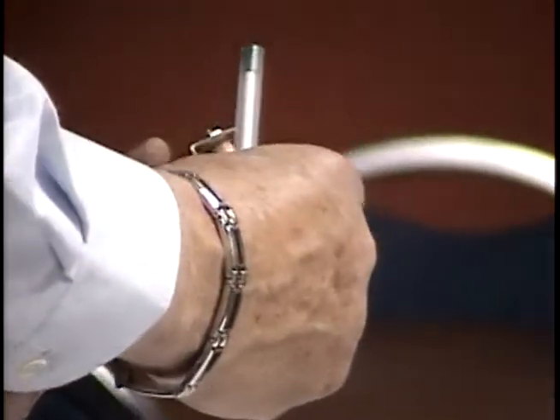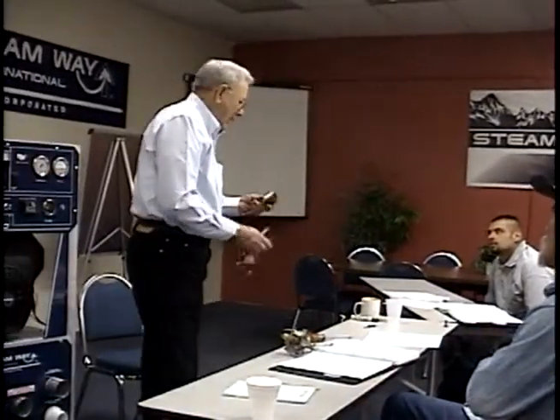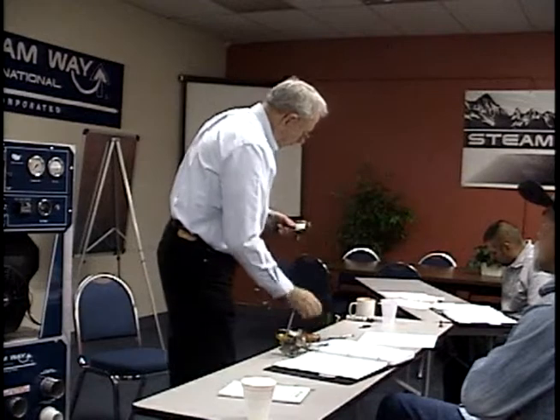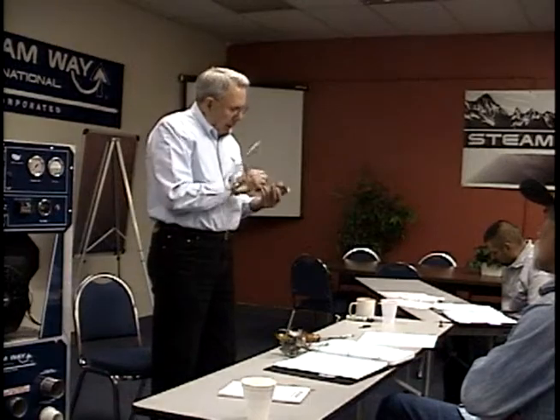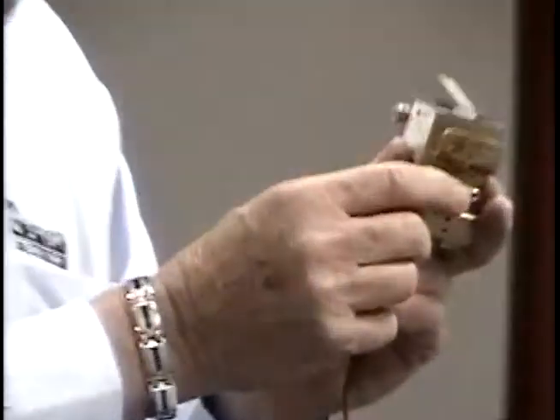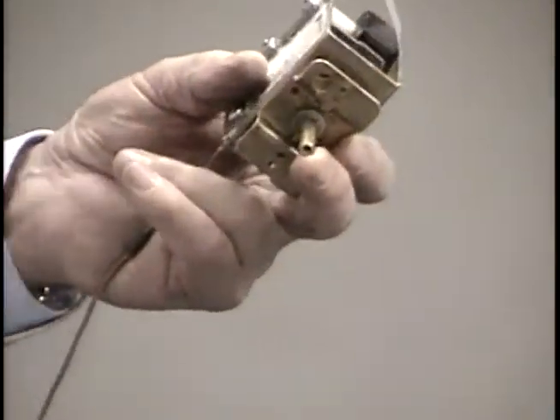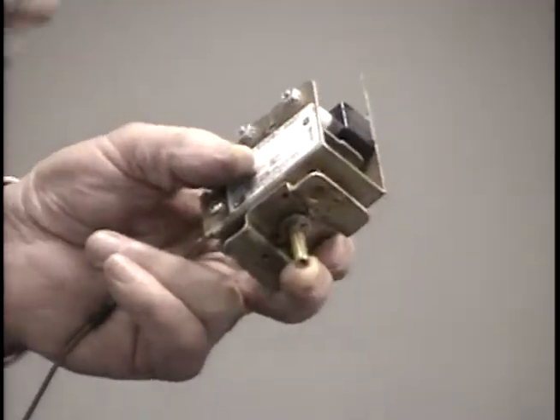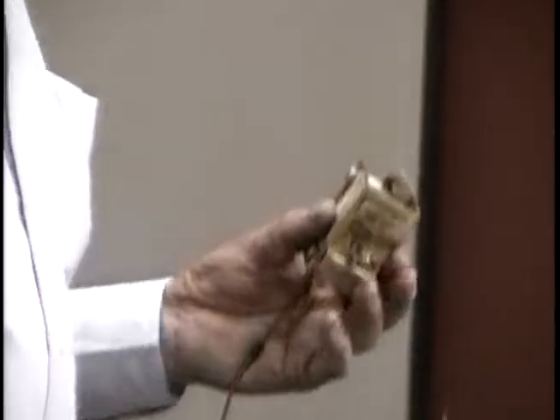See the little round bronze plate? As it swells up, it kicks the switch off. As it cools down, it kicks the switch back on. So this circuit is really more mechanical than electrical. The only electrical part is the switch closed, switch open, just like we saw on our diagram. By the way, we recalibrated those, and they can be recalibrated by taking the knob off, and up through the little hollow shaft you put an Allen wrench in there, and they can be recalibrated. If you got a heater overrun or something that threw it out of calibration, you come back and recalibrate it. So it's a very good switch.